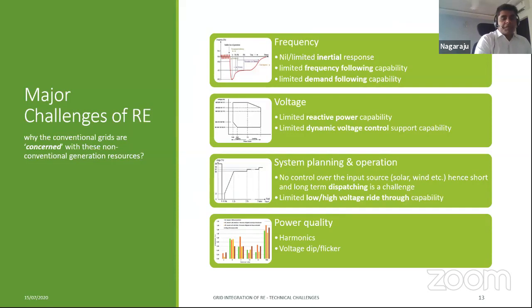All right, in terms of challenges, I have divided the renewable energy challenges to the grid into four parts based on the fundamental parameters of the power grid, as well as the operational issues. The fundamental parameters of any power grid are frequency and voltage. And there are operational issues in terms of actual power quality, because the grid operator is responsible for providing standard quality power so that the grid consumers do not complain. And there are other planning issues we will touch upon. So let's go one by one.